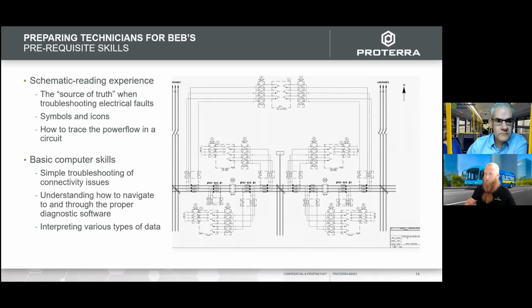If the door does not open, even though you're commanding it open, I'd hope a technician would understand that if the bus is off, that's probably not going to cause an output. I can go into this circuit and determine, okay, I'm not seeing an output from the controller, and the only thing between the controller and the door, or the controller and the energy storage system, would be the circuitry itself—the wiring. So I'm almost guaranteed it's a wiring issue.